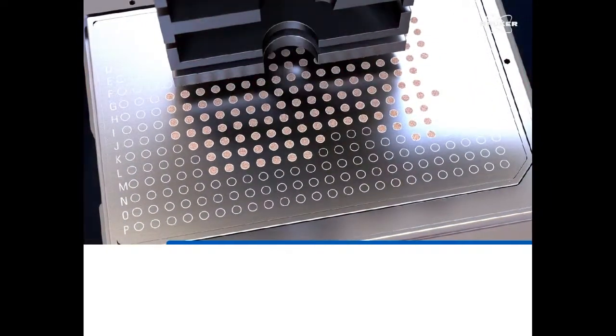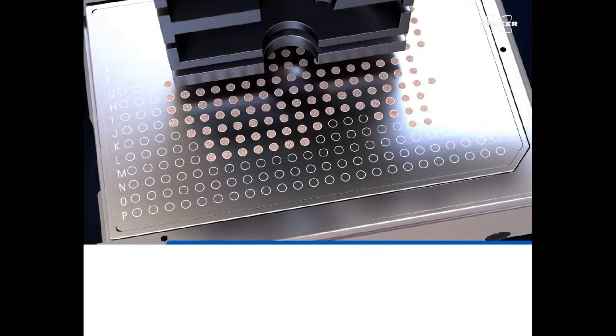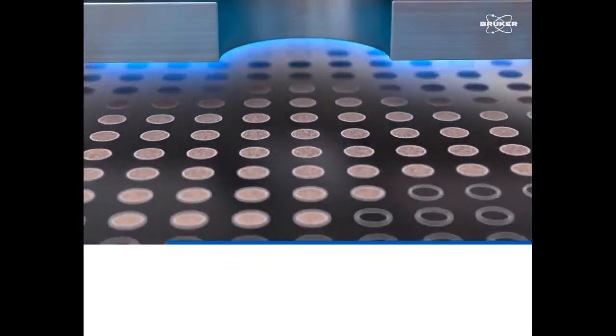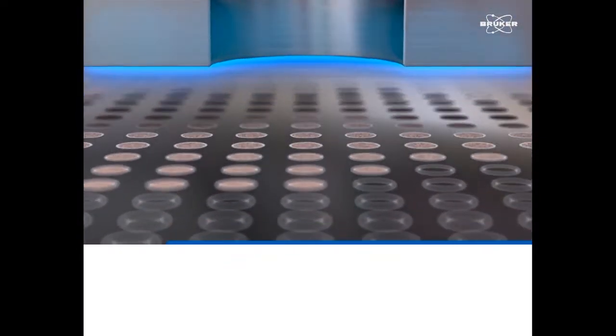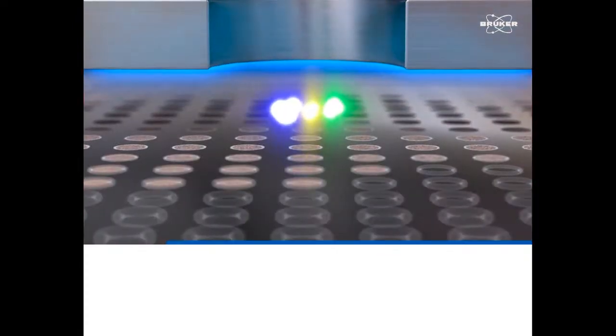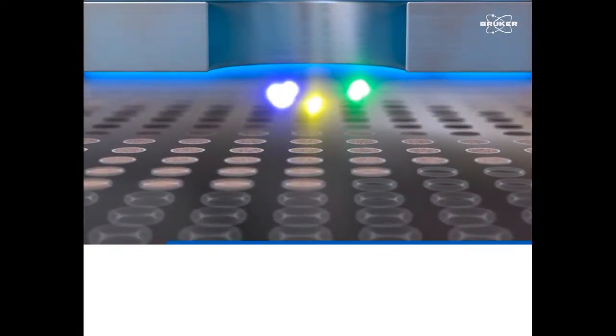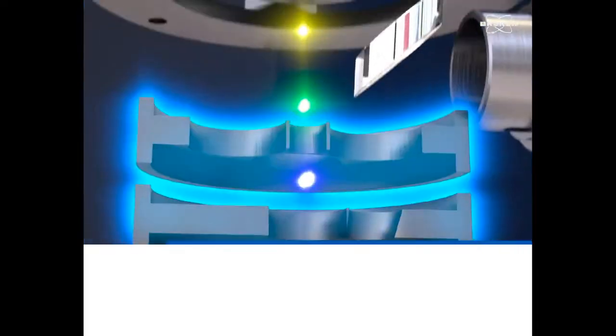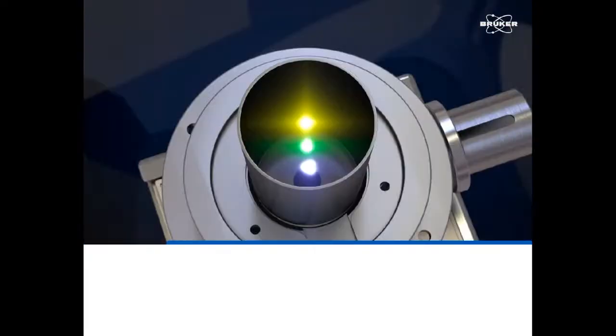Samples are co-crystallized with a suitable matrix on a sample carrier. The samples are vaporized by the laser into a vacuum while being ionized at the same time. During this process, the sample molecules can become excited. The now charged and excited particles are accelerated through the application of a high voltage, and fragmentation can occur as they travel through the flight tube.